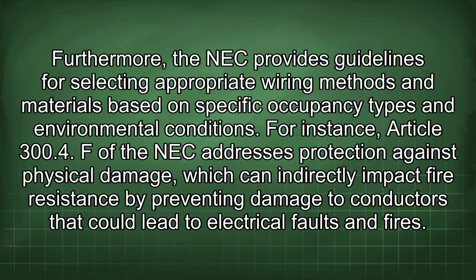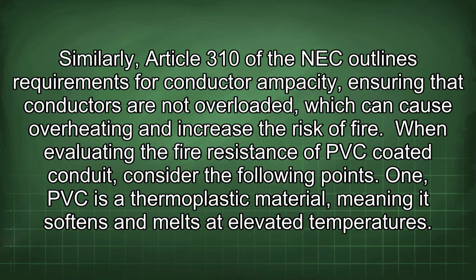Furthermore, the NEC provides guidelines for selecting appropriate wiring methods and materials based on specific occupancy types and environmental conditions. For instance, Article 300.4(F) of the NEC addresses protection against physical damage, which can indirectly impact fire resistance by preventing damage to conductors that could lead to electrical faults and fires. Similarly, Article 310 of the NEC outlines requirements for conductor ampacity, ensuring that conductors are not overloaded, which can cause overheating and increase the risk of fire.